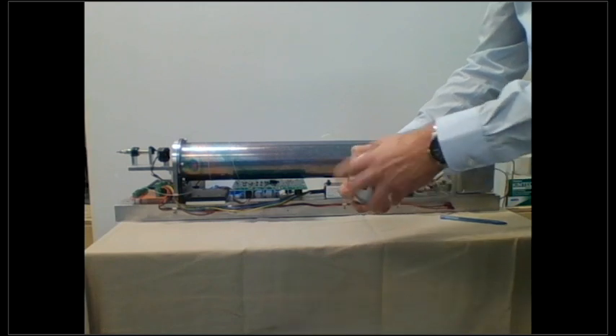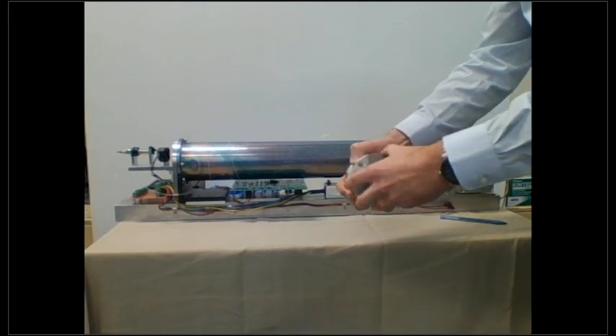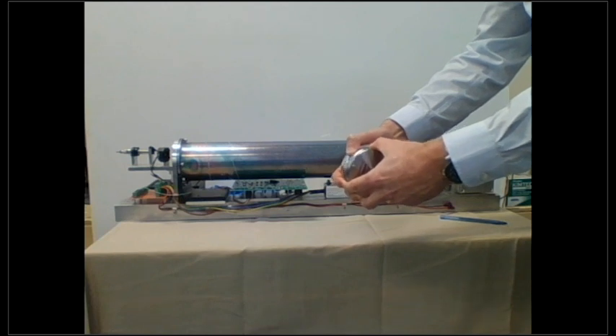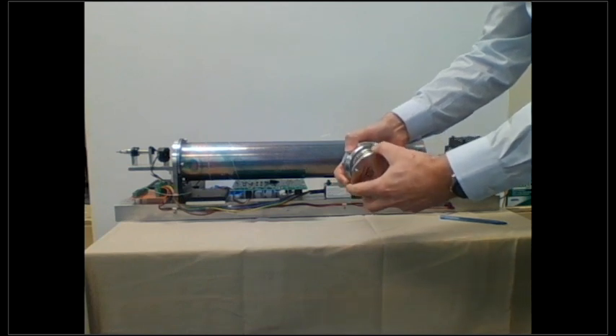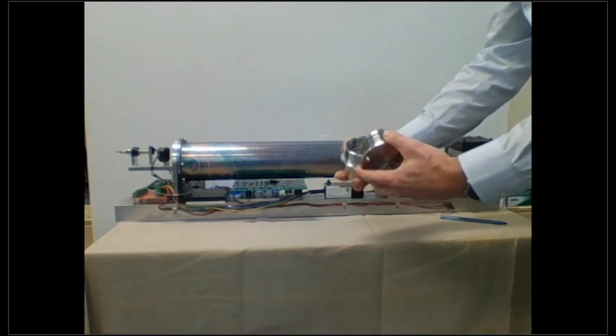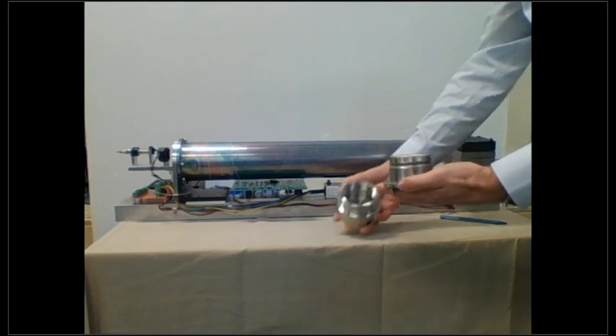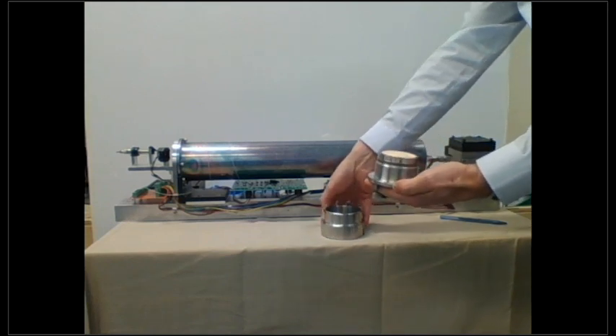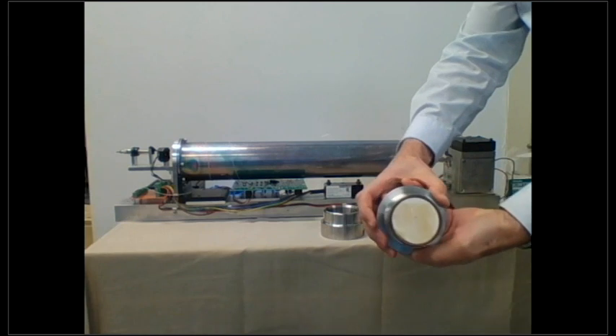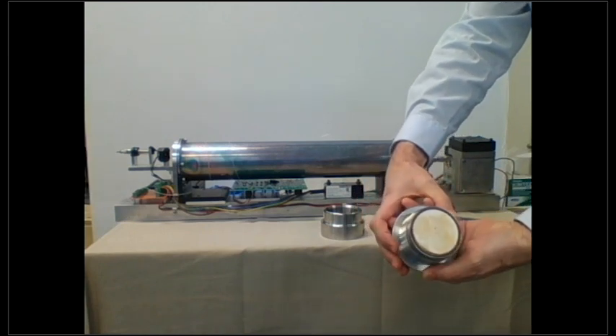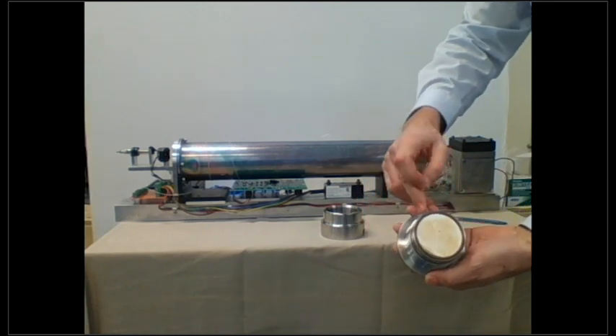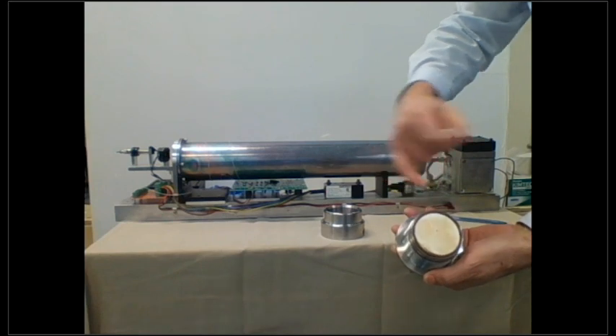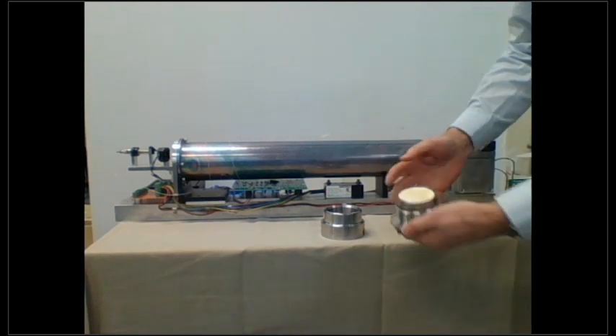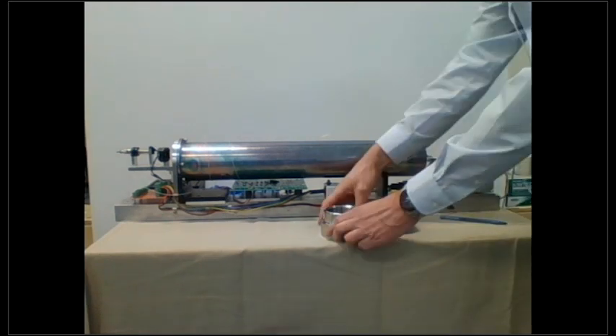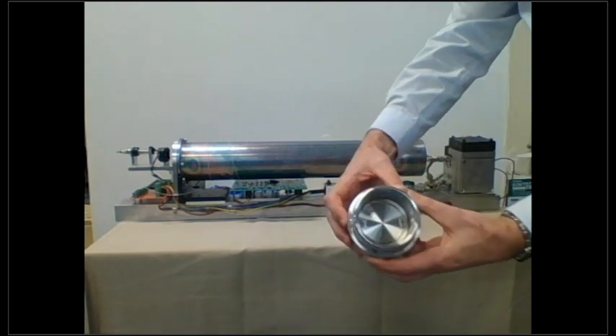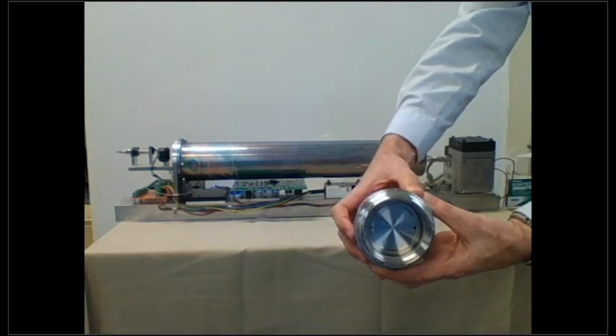So the maintenance on these items is relatively simple. It has a screw-off cap, so when it's all done up, you can use a screwdriver or something along those lines to pry open the device. It just simply screws apart and gives you access to the membrane. Now I'm doing this on the bench, but there's no reason to unmount it from the analyzer panel. This can basically be done in situ.